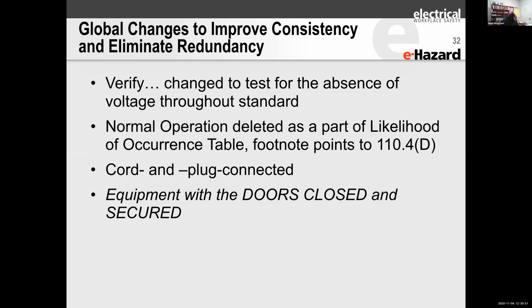And then equipment with doors closed and secured was put in because in some cases, the equipment is perfectly safe. Arc-resistant equipment, for example, is perfectly safe with no PPE as long as the doors are closed and secured. But if they're not closed and secured, then arc-resistant equipment, in many cases, unless it's arc quenching, is actually the same as regular switchgear because it can still blow up inside. It just normally shunts the energy away, but it has to be closed and properly secured.